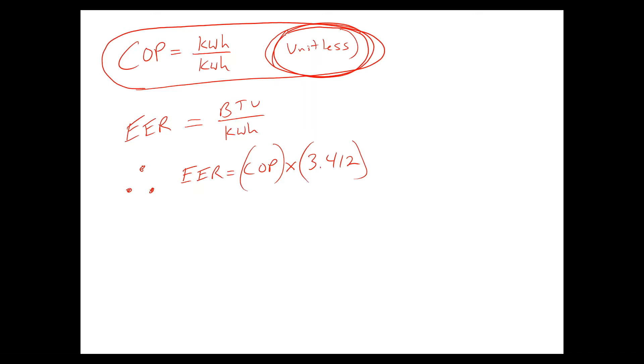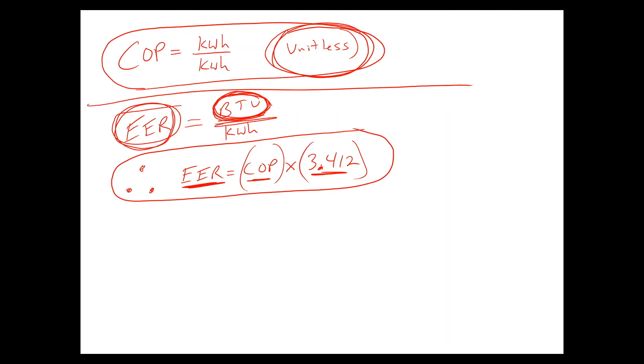But when you come to the United States, we often don't use COP because we use a different term that has BTUs on the numerator. And because we have BTUs, because that's how we like to express heat flows in the United States, because we have BTU over kilowatt hour, it's no longer unitless. So we use this term called energy efficiency ratio. In fact, if you know the COP, you can always find the EER because they're linearly related. So the EER equals the COP times 3.412, which is basically just accounting for the difference between kilowatt hours and BTUs. So we have, we've talked about COP, we've talked about energy efficiency ratio. There's two more concepts I want to get across.